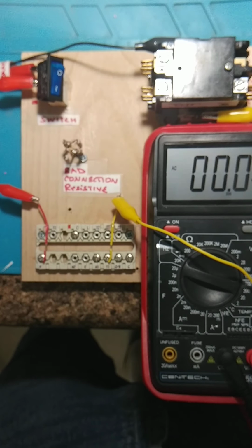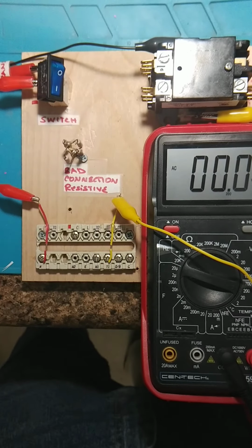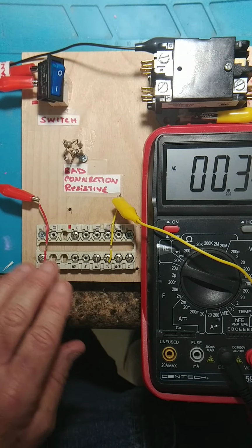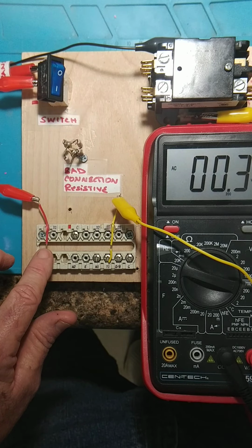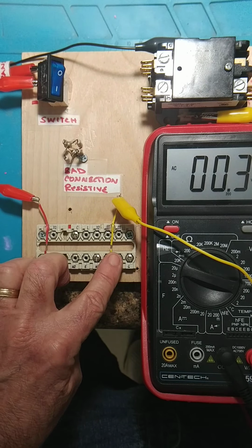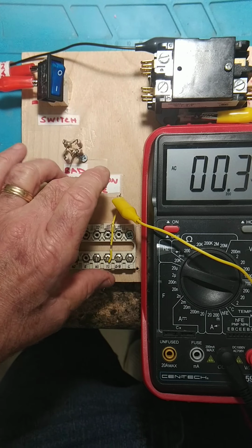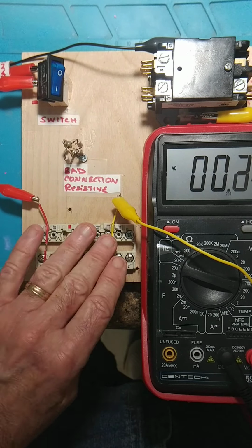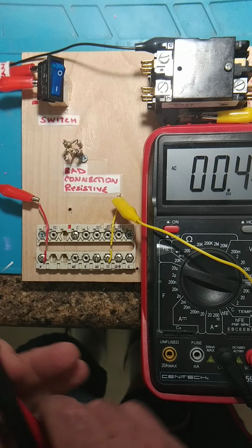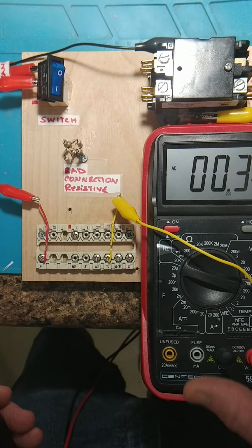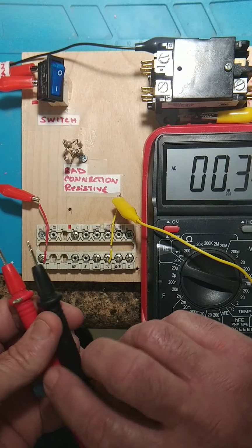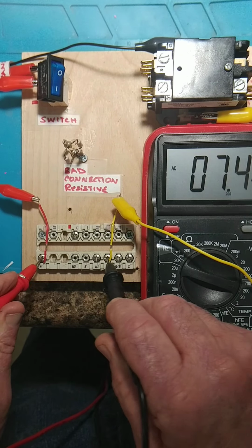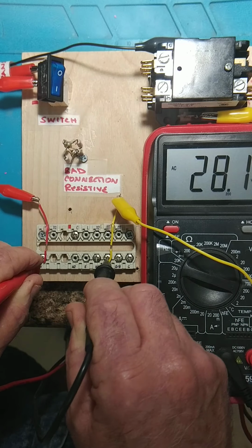So I'm going to go ahead and turn the power on, and nothing is going to be coming on because my thermostat is not closed. So my thermostat's not calling. I do not have a connection between R and Y, which would be within the thermostat. So this would be as if you had the thermostat off the sub base, and so it's not calling for cooling. So I've got my voltmeter set to volts AC. I'm just going to check, and across R to Y, I have 28 volts.